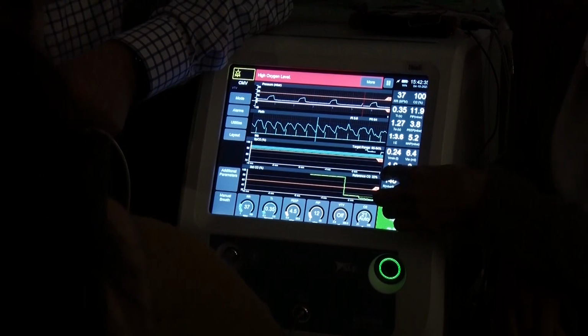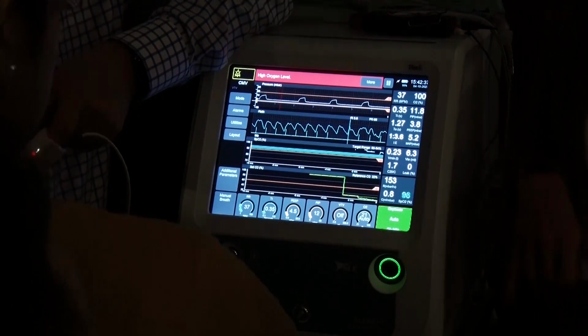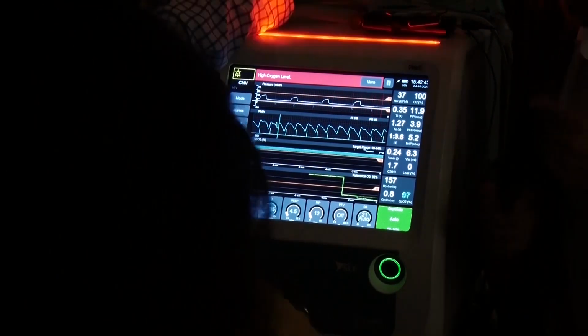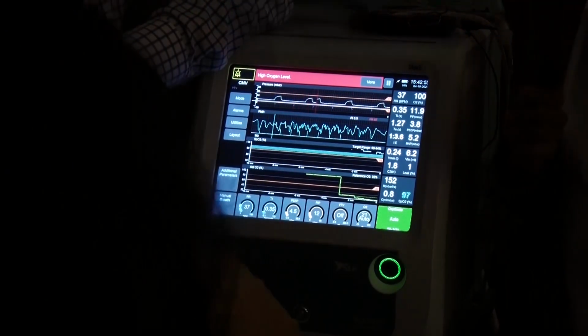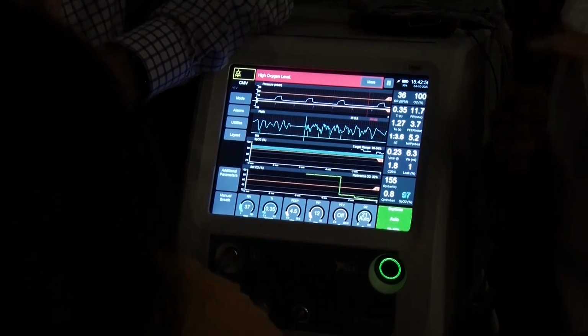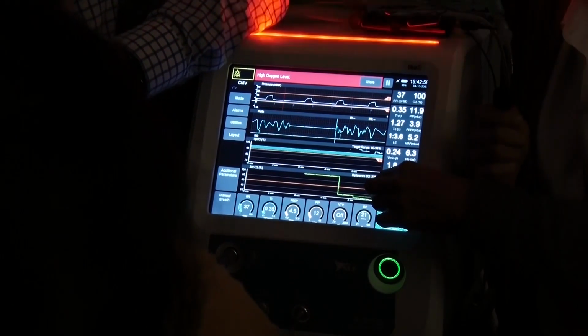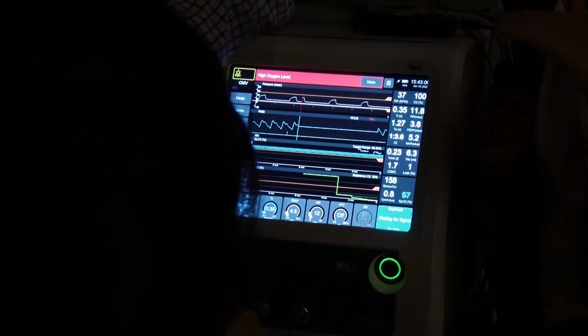Depending on where you are when you start, here you are at 30. If you use Oxygenie, the reference O2 is a value that the ventilator has calculated, the FiO2 requirement to keep your patient within the target outside of the episode of hyper or hypoxemia. So it's telling you the base. We don't have it in the trends, but I will ask the team to note this one, because it tells you whether the requirement is increasing or not.